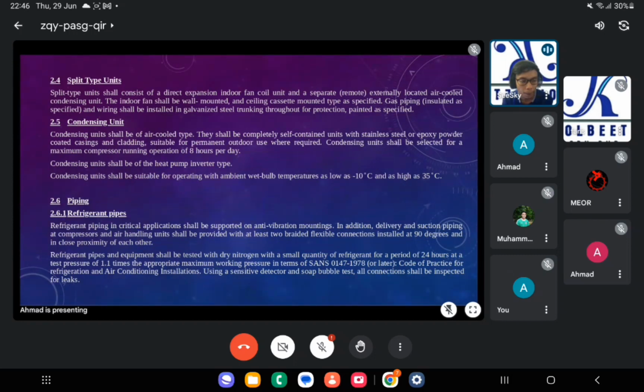2.6 Piping. 2.6.1 Refrigerant pipe. Refrigerant piping in critical application shall be supported on anti-vibration mounting. In addition, discharge and suction piping at the compressor and air handling unit shall be provided with at least two braided flexible connections installed at 90 degrees and in close proximity of each other.